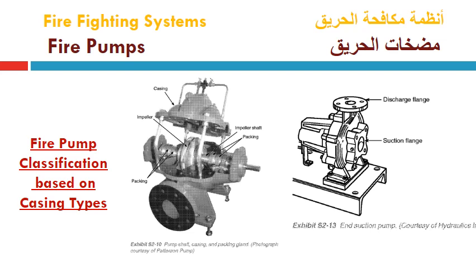However, the right hand side figure shows an end suction pump. The shaft is installed horizontally here and the impeller is affixed perpendicular to it. This is the suction flange with the suction flange bolts from here, and this is the pressure tap. Then the flow goes through the impeller eye of the single suction single stage impeller, and according to the rotational motion of the shaft in this direction, the flow is collected and discharged from the impeller outlet to the volute casing until it reaches the discharge flange, which is located here perpendicular to the suction flange. So in this type, the suction flange and discharge flange are commonly perpendicular to each other, as listed before in the previous lecture.